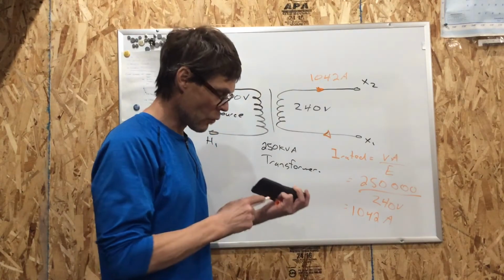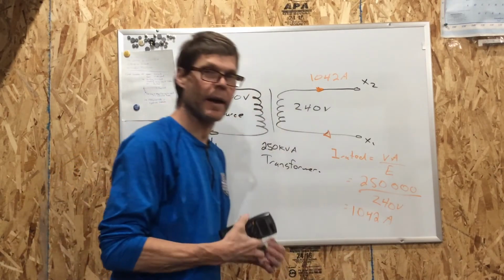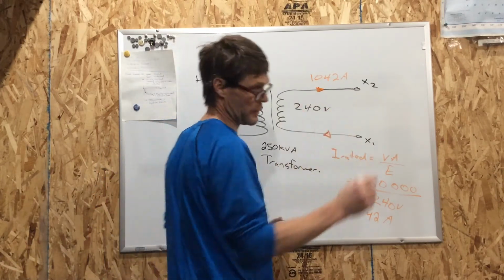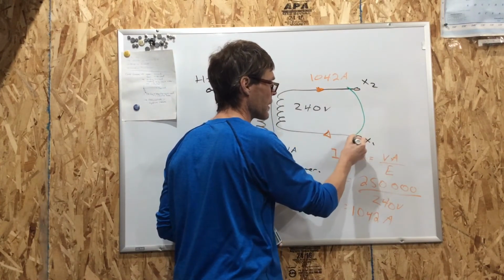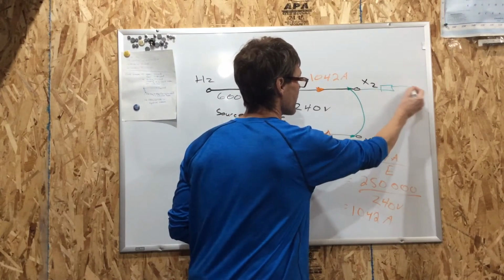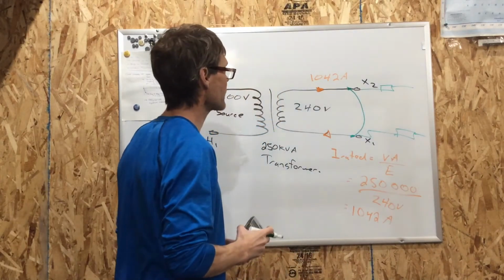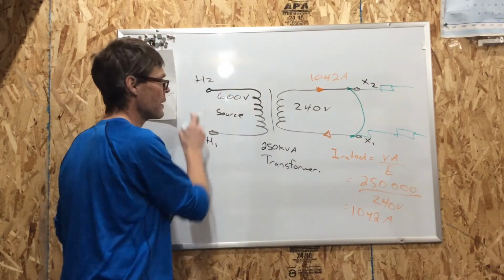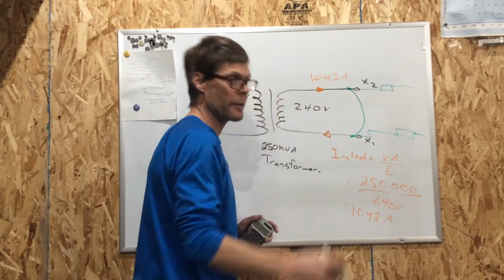All right. Now, what is short circuit? Short circuit, what we're going to say is that we have had a line-to-line fault on our secondary. So picture this. Don't go do it. Picture this, that something metal has fallen across here. And let's just picture for a moment that our secondary fuses are downstream, okay? So now we're relying on high voltage fuses. But right now, we've released an incredible amount of energy.